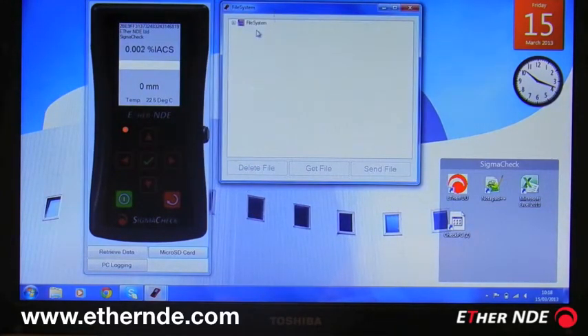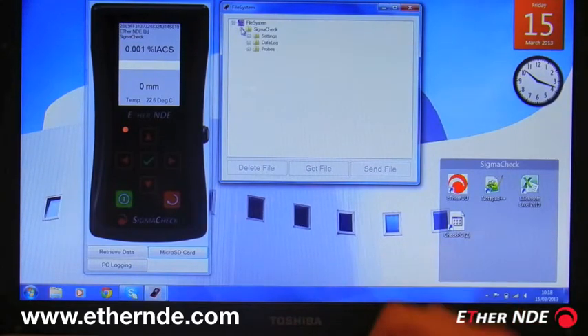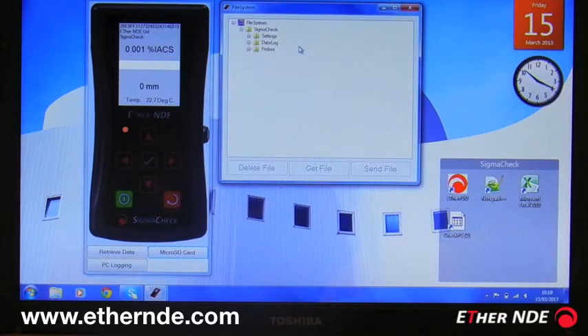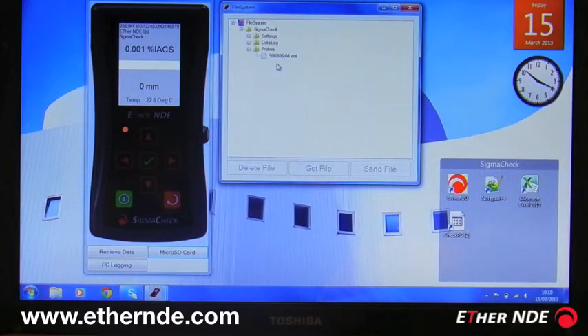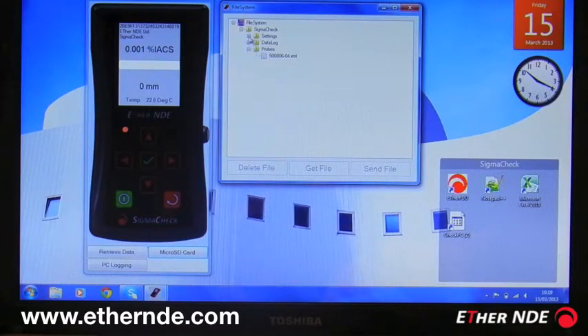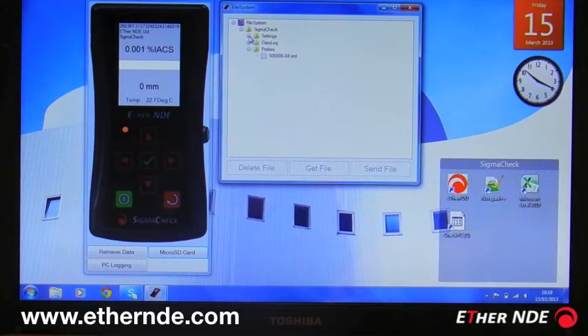So if I expand the file system tab and open the SigmaCheck folder, you have a settings, a data log, and a probes folder. Within the probes folder you can see files for any probes that are configured for this instrument. The settings file contains the settings required by the instrument, so not really to be modified.